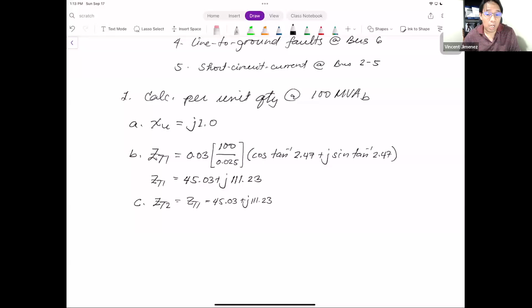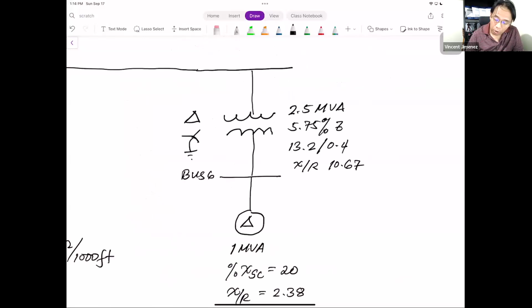Okay, now let's calculate for the transformer 3, yung 3-phase transformer natin. This is 5.75% base at 2.5. So we need to convert to 100 MVA base. Noticeable that bus 6 is 400, yung bus sa taas is 13.2, there's no change in base voltages.